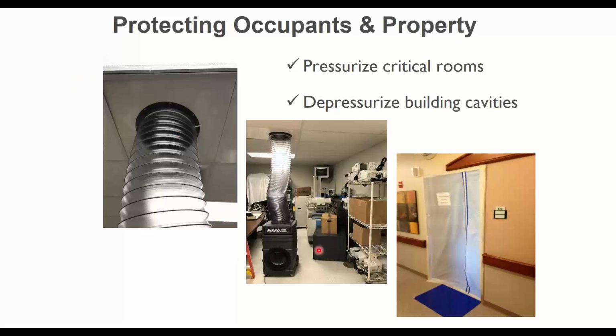The reason you do that is because when we're sealing this ductwork from the inside out, those glue balls are going down the duct, finding the crack, leaking out the crack, and sealing the crack as they go out. But some of them are going out, so they're going to end up in the room, or in the rooms, plural. If all the ductwork's above the ceiling, usually not a big deal. Most of it stays above the ceiling. But if you have exposed ductwork, then you start seeing more of that glue in the air coming down. So you run these fans to suck that air out of the room and duct it out, or run a scrubber, which is nothing more than a cube, if you will, that has a fan on it, no duct, but a bunch of filters on every side of it.